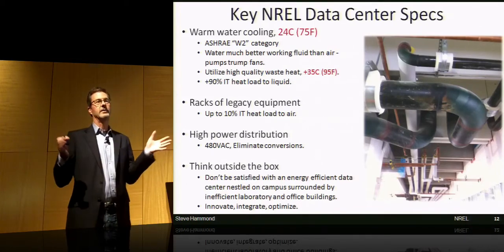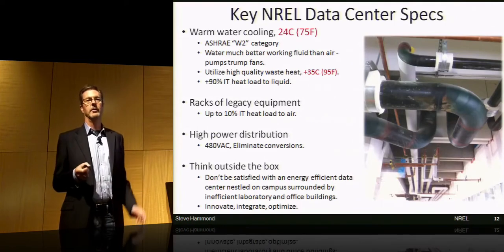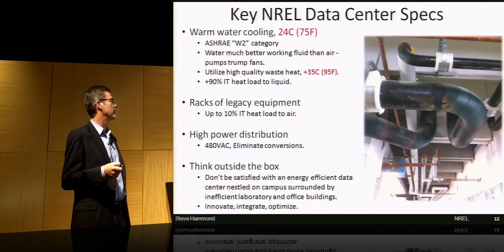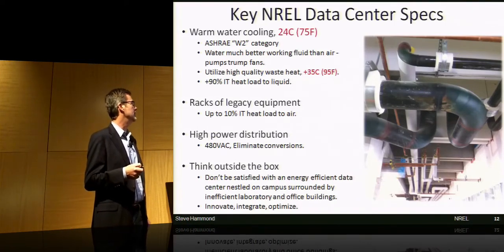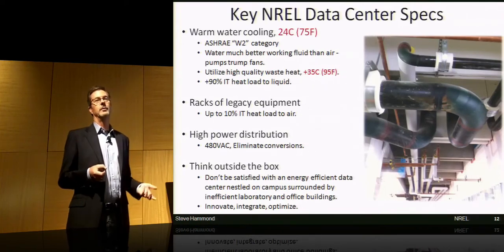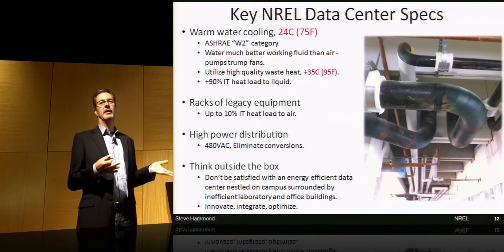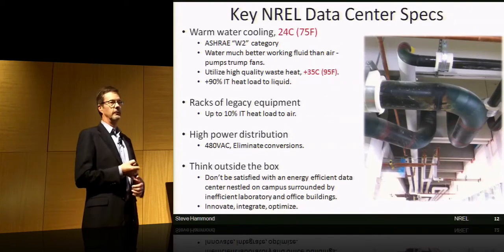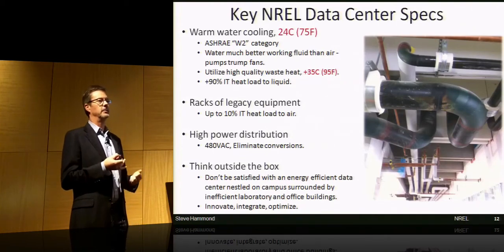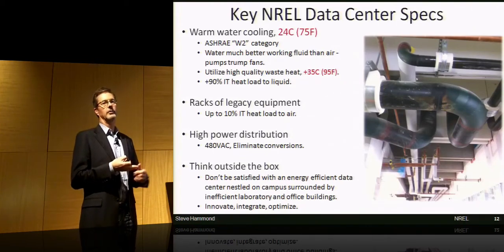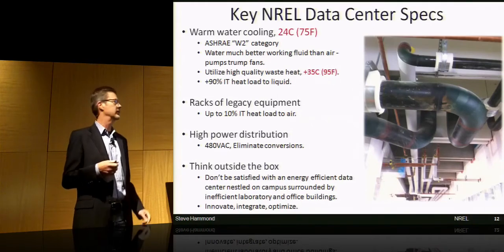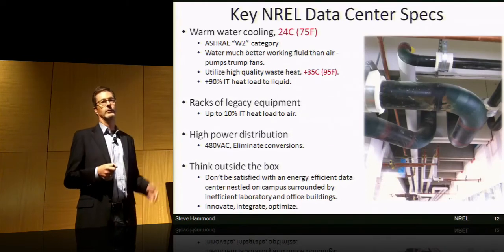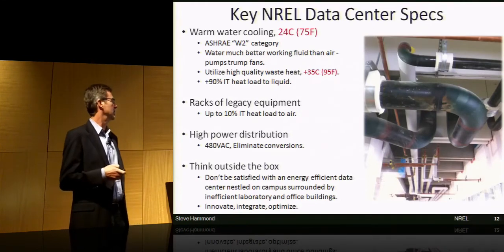Our racks are sitting outside in the middle of the room, and they're more or less room neutral in terms of heat. But we do have legacy equipment, so you can't completely eliminate the air side. Our Lustre file system, networking, control nodes, and some miscellaneous servers fill 2 full rows that are hot aisle contained.